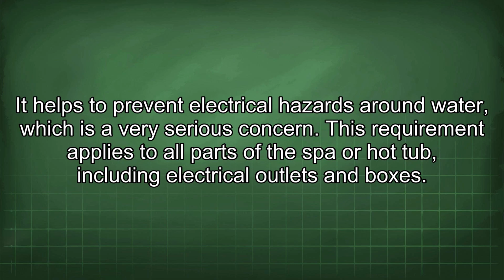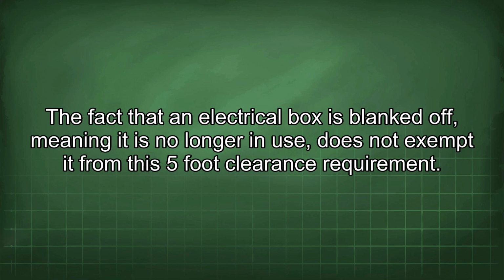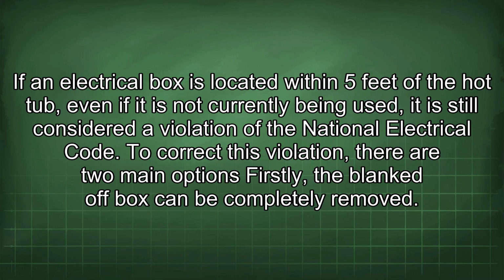It helps to prevent electrical hazards around water, which is a very serious concern. This requirement applies to all parts of the spa or hot tub, including electrical outlets and boxes. The fact that an electrical box is blanked off, meaning it is no longer in use, does not exempt it from this 5-foot clearance requirement. If an electrical box is located within 5 feet of the hot tub, even if it is not currently being used, it is still considered a violation of the National Electrical Code.